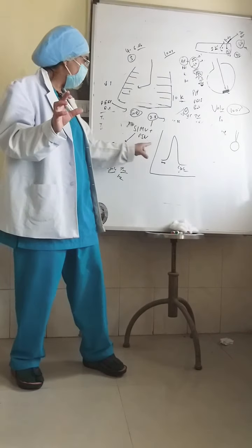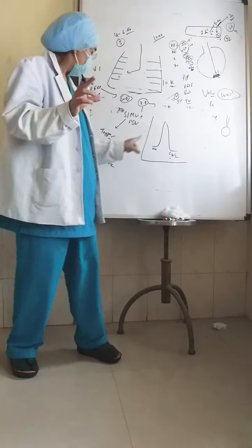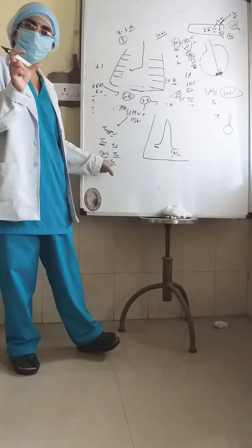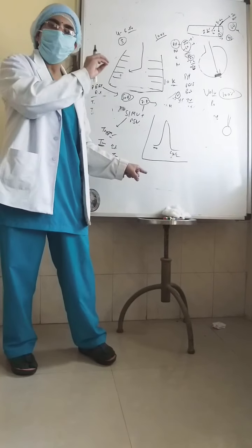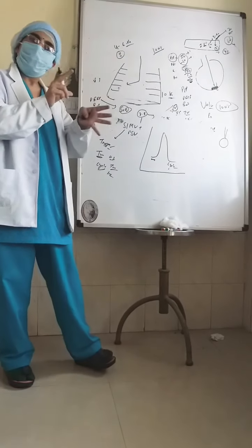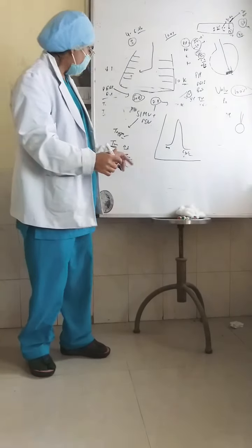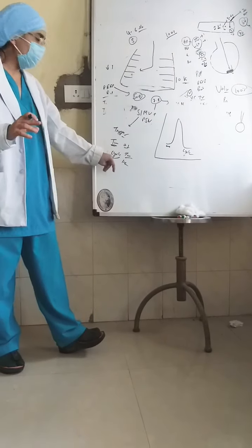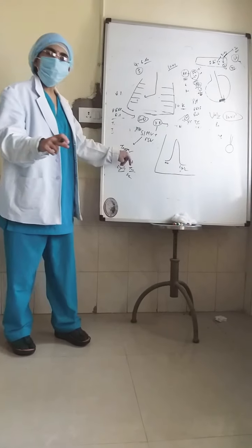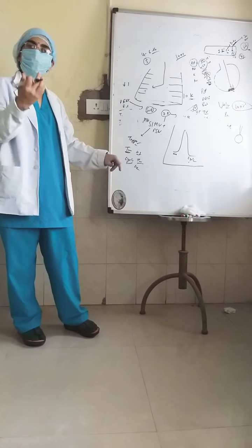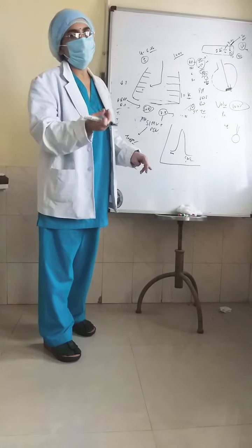So in pressure cycle, it is a fixed pressure which is delivered. In time cycle, it is the time frame in which whatever volume the ventilator wanted to deliver is delivered. After that certain time, the ventilator is going to terminate the breath. So just remember, cycle is something which terminates the ventilation, and triggering is something which initiates the ventilation. So what can trigger it? You can put a time trigger, you can put a flow trigger.